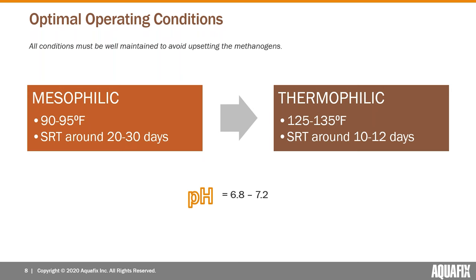Basic operating conditions: you'd have either a mesophilic or thermophilic digester, each with specific temperature ranges. The optimal pH range for methane production is 6.8 to 7.2, though many digesters run at 7.5–7.7 with still good activity. However, above pH 7.5 there is added risk if you have a lot of ammonia in your waste stream — ammonium begins converting to ammonia, and while ammonium is generally non-toxic, ammonia can be toxic to anaerobic digesters.